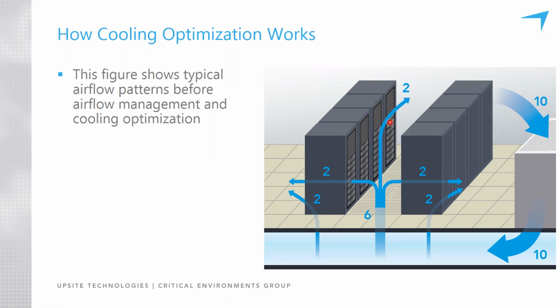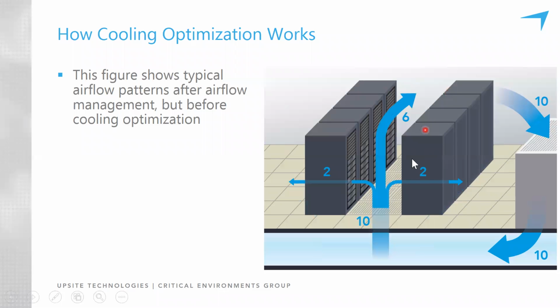So when the IT equipment is sucking up 4 units of air, but 6 are supplied to the cold aisle, then we have 2 units of air leaving the cold aisle as bypass airflow. So what do we need to do in this room? We need to fix, obviously, the bypass airflow coming out of the unsealed cable openings. And when we do that, we've now forced all the conditioned air to come out of openings in the cold aisle. And that's the way it should be.